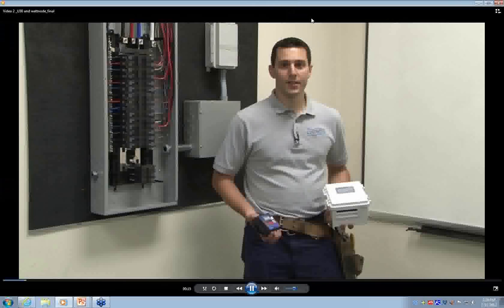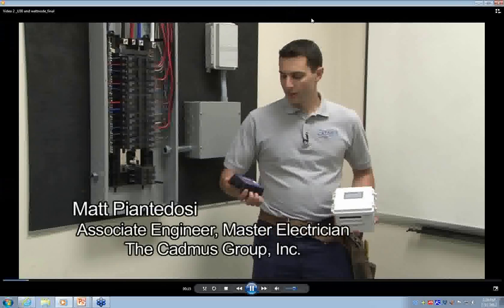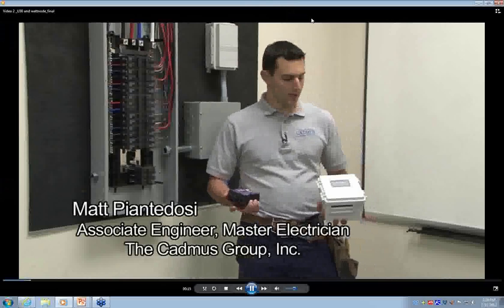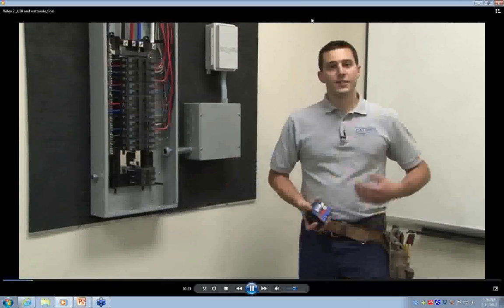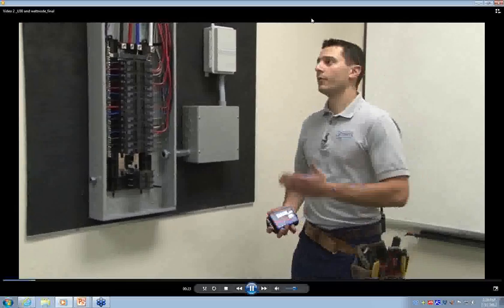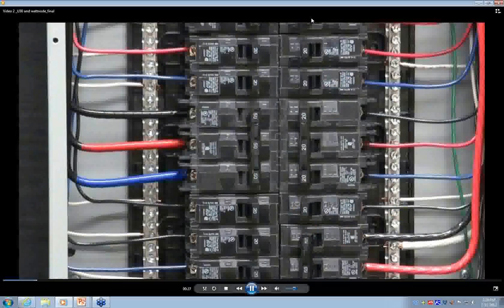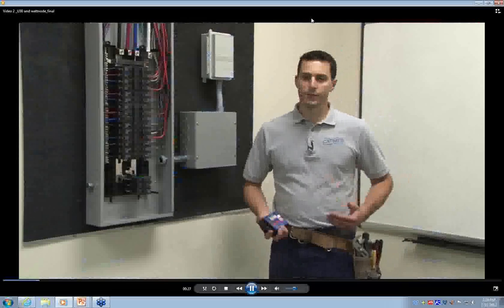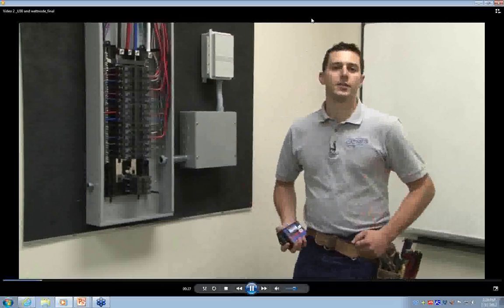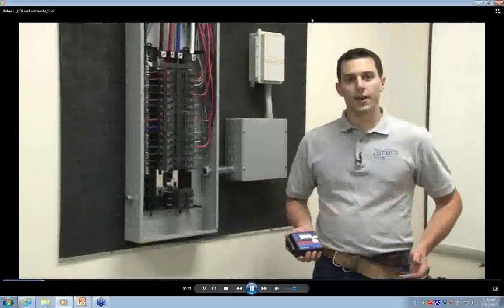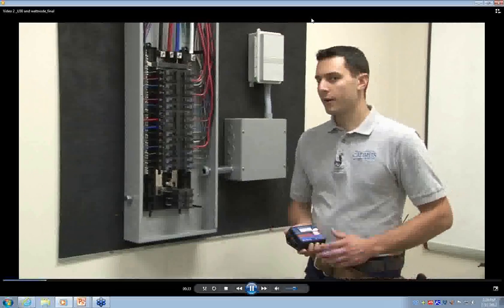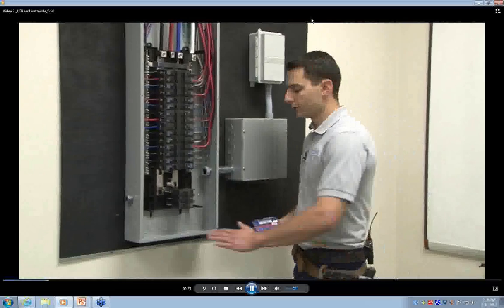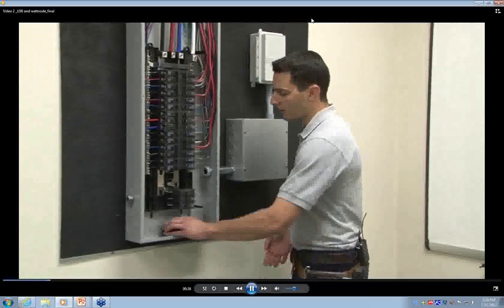We will now monitor the energy on a single circuit using a watt node and a HOBO U30. Once again, we'll be doing this on our display panel board, which is de-energized, so we can focus on the equipment installation. If this was a live panel board, I'd be wearing the necessary safety gear. We'll start out by identifying a safe location for our watt node. For this installation, we'll use the bottom of this panel board right here.